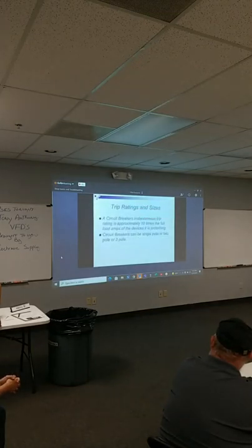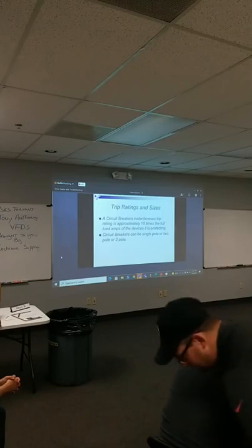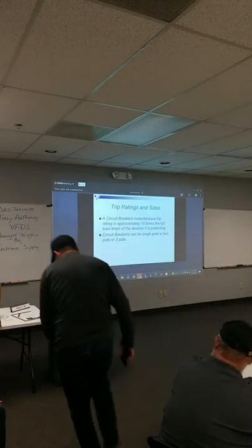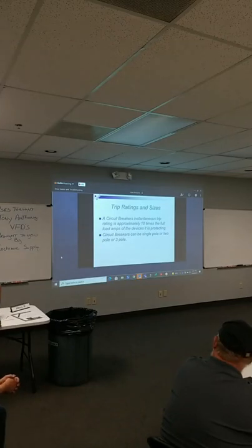Circuit breakers, the nice thing about them is they provide an instantaneous trip rating of approximately 10 times the full load amps of the device they're protecting, and you can get them in single pole, two pole, or three pole. The reason this is important with a drive is we can do a single phase input to a drive. So if you've got an application where you've only got single phase 240 available and you want to run a three phase motor, we can do that. You would have a two pole breaker there. So that's something to think about. If you've got any questions about that, we can discuss it.